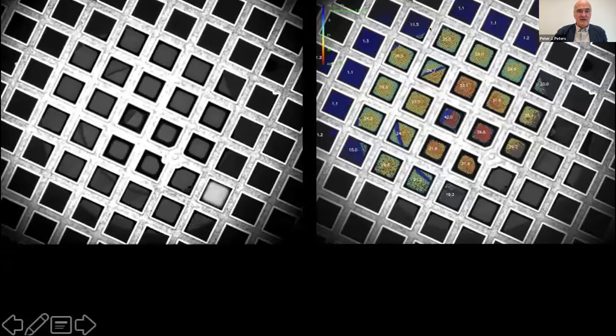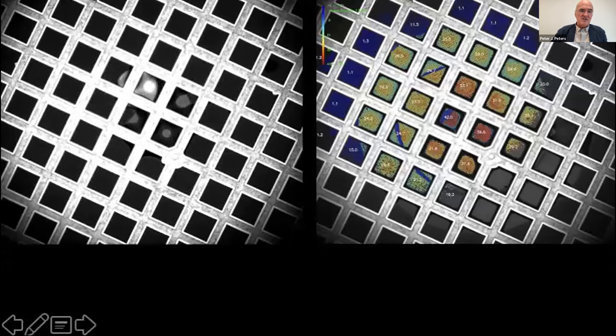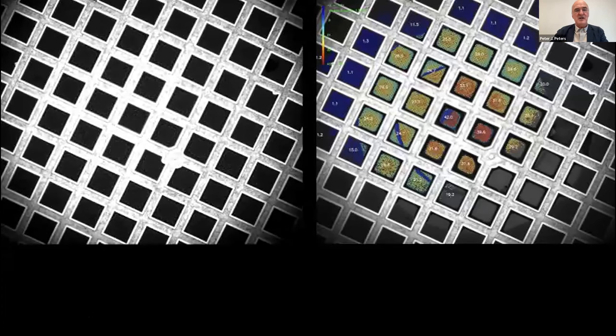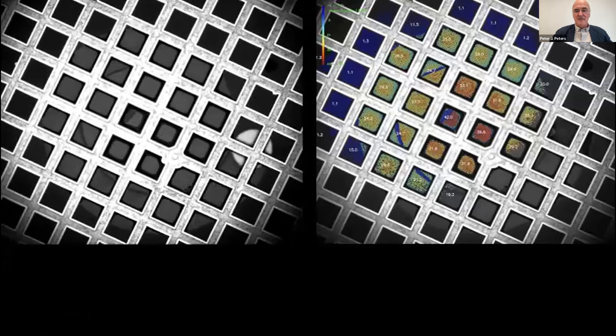You can also take a picture one second later, and if it becomes thinner, you have evaporation, and you will immediately notice this. If you have condensation of water, it becomes thicker. So that is both bad, and you need to work precisely at dew point in a special controlled climate chamber. And so these are the elements that are in there.